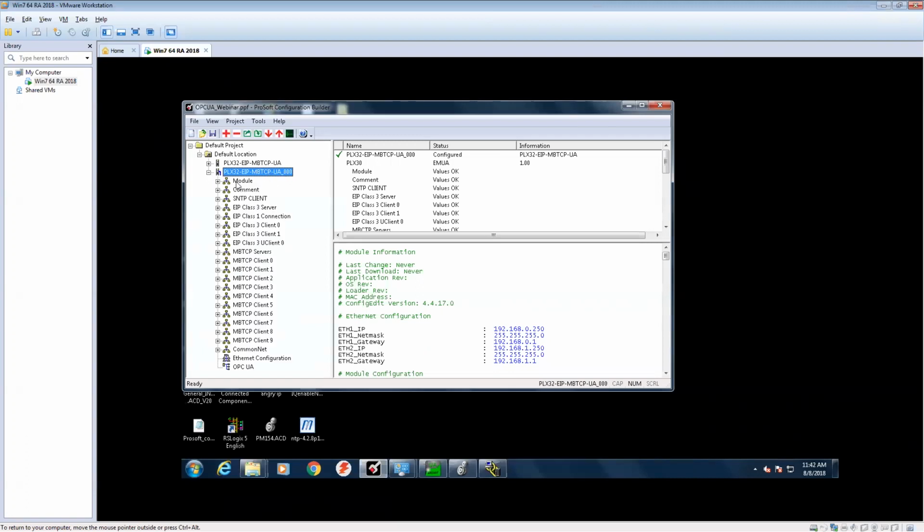These are all the different parameters, depending on what you're doing with the gateway. I know there's probably not a whole lot of applications where Ethernet IP, Modbus TCP, and OPC UA will be used at the same time. And typically it'll probably be one, either Modbus TCP or Ethernet IP. So depending on your application, you may not have to do a whole lot in here. For instance, if you have a Logix processor or even a PLC5 or SLC issuing messages to the gateway to retrieve OPC UA data, then there is absolutely nothing you need to do on the Ethernet IP side, because it's automatically an Ethernet IP server.